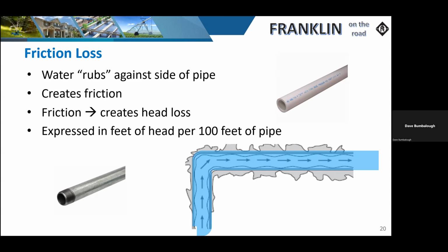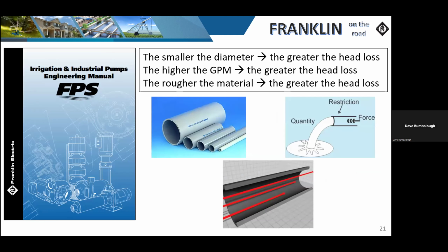So as we look at friction loss, the size of the pipe, the material of construction, and the length all contribute to that friction loss. Plus, on top of that, we have the fittings and check valves and other things in that line that add up into friction loss that we sometimes overlook. The material of construction makes a big difference. The slicker that material is, such as some of your PVCs, the easier the water flows. So the calculation for that is less than, let's say, steel pipe or galvanized pipe. It's a little rougher material, therefore friction loss goes up with those materials. So you've got to be careful which ones you're choosing.